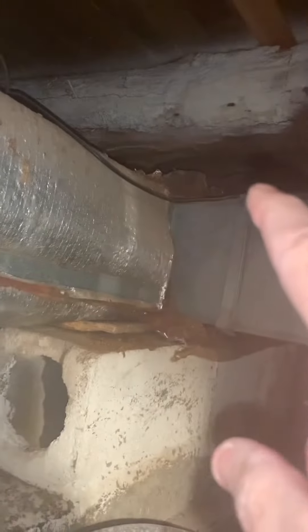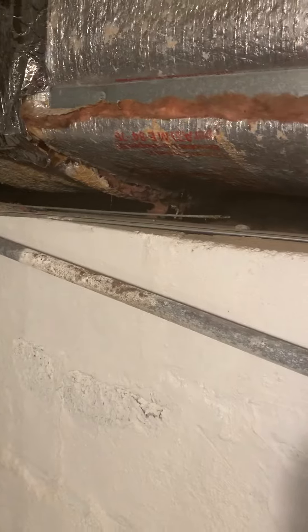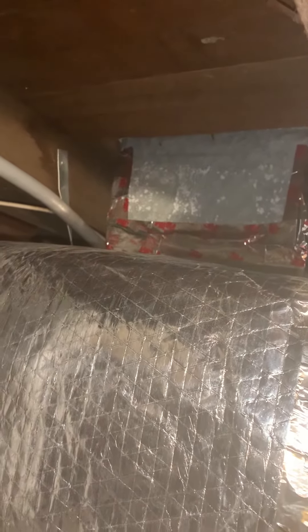We've got a run that comes off and goes to the first floor — right above you — and then a trunk line running down. It's not the best installation; it's all kind of falling apart and falling off. We do have a duct going up to the second floor. This is 14 by 14 and it's been hodgepodged together — not a solid piece of 14 by 14 duct. We thought about a damper there; we may have to do some modifications with that.